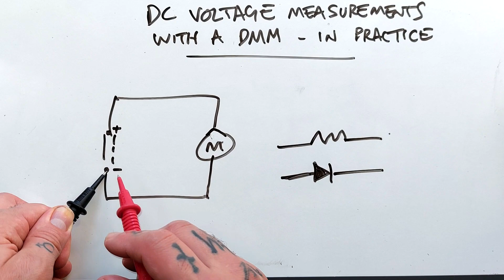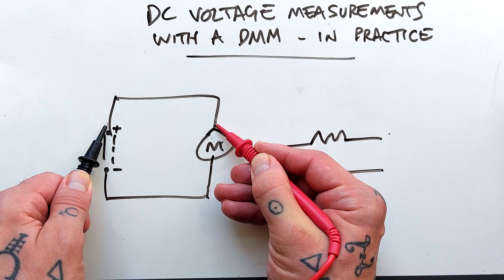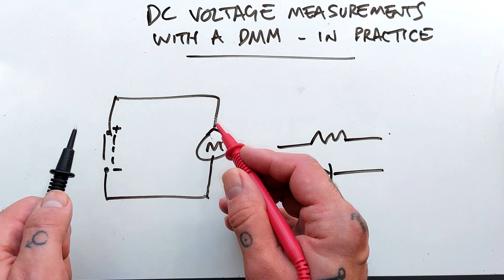So in practice, how am I actually using the probes? This here represents positive and negative output of a DC power supply, going to an active component here. I've chosen to draw a DC motor. As I said earlier, you're not going to see a simple schematic like that—this is going to be one of multiple parallel circuits in a much more complicated schematic. I'm going to put my black probe on circuit ground, and I'll talk more about circuit ground later in the video. So if this is like a 12 volt motor, I want to see a reading something like 12 volts there to know it's getting enough energy. I could measure voltage drop here to make sure it's low enough, which shows the resistance of the connectors leading into the input of the motor are low enough. I could also use a continuity tester to see if that's beeping, to see whether that resistance is low enough to indicate a healthy connection.